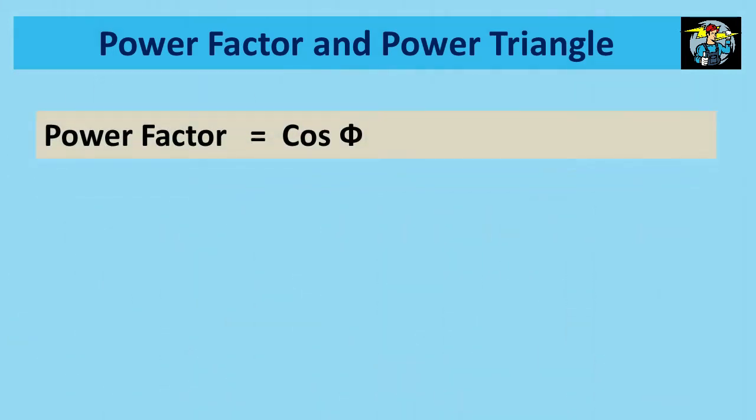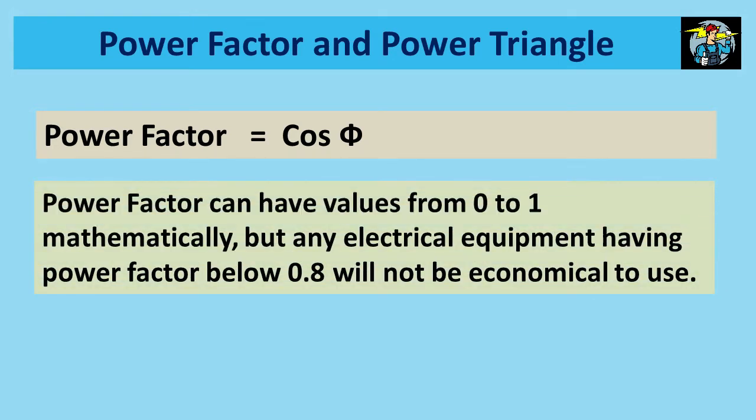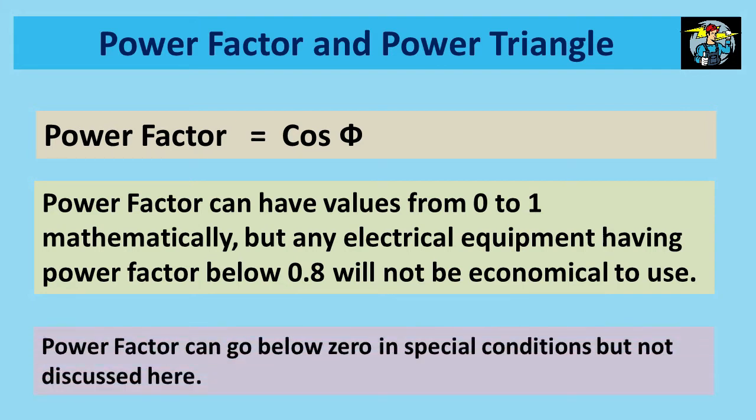Power factor is also called cos phi and you will have seen this on name plates of induction motors, generators, or on any other relevant electrical equipment. Power factor can have values from 0 to 1 mathematically, but any electrical equipment having power factor below 0.8 will not be economical to use. Power factor can go below 0 in special conditions, but not discussed here.